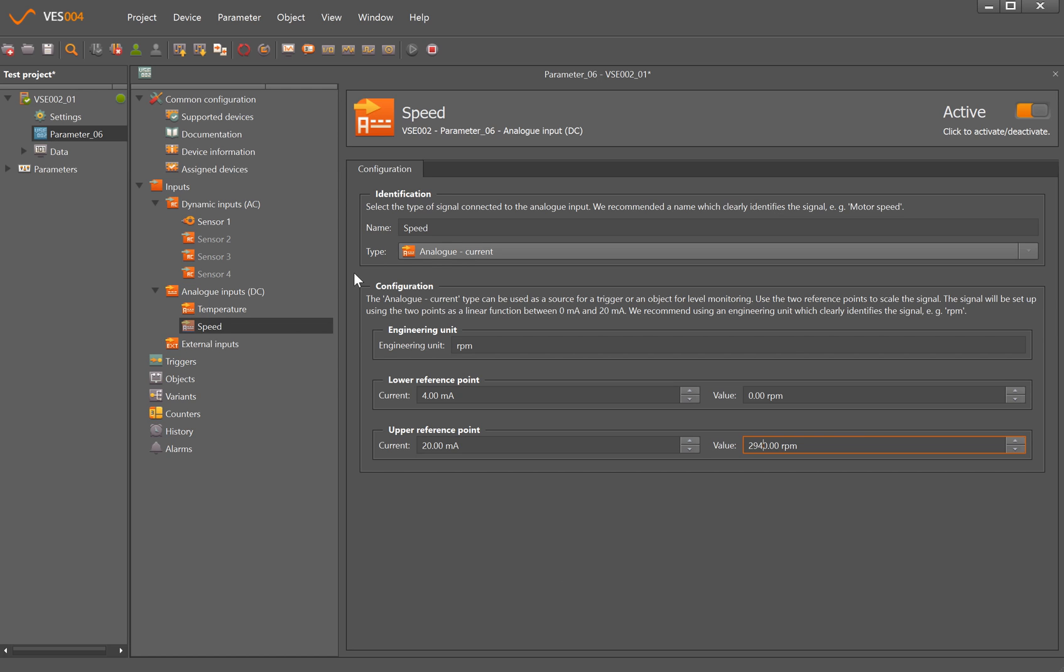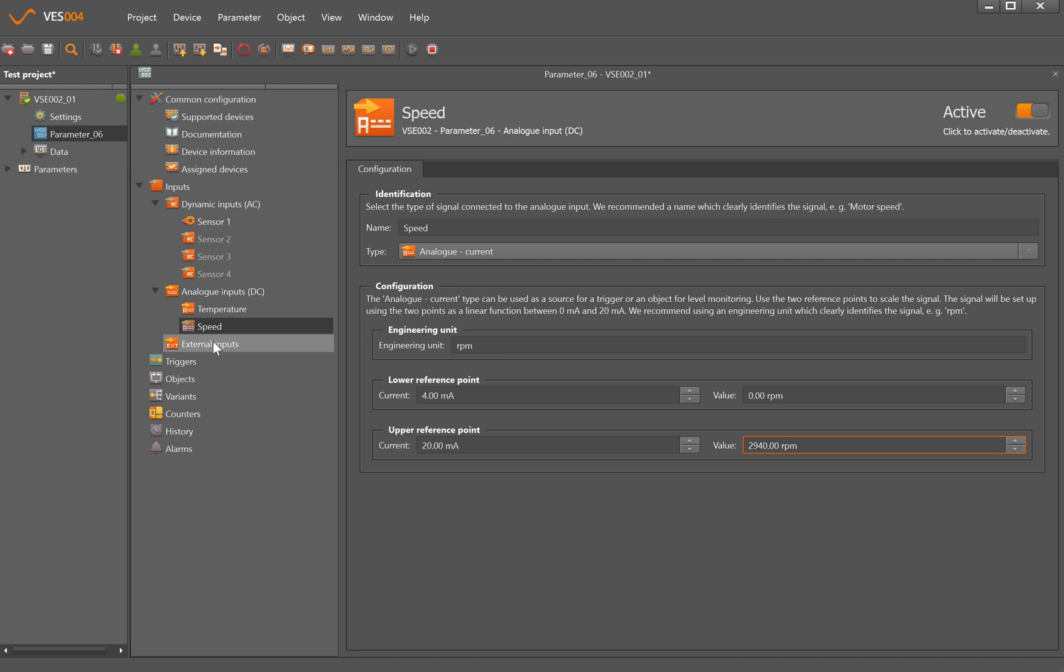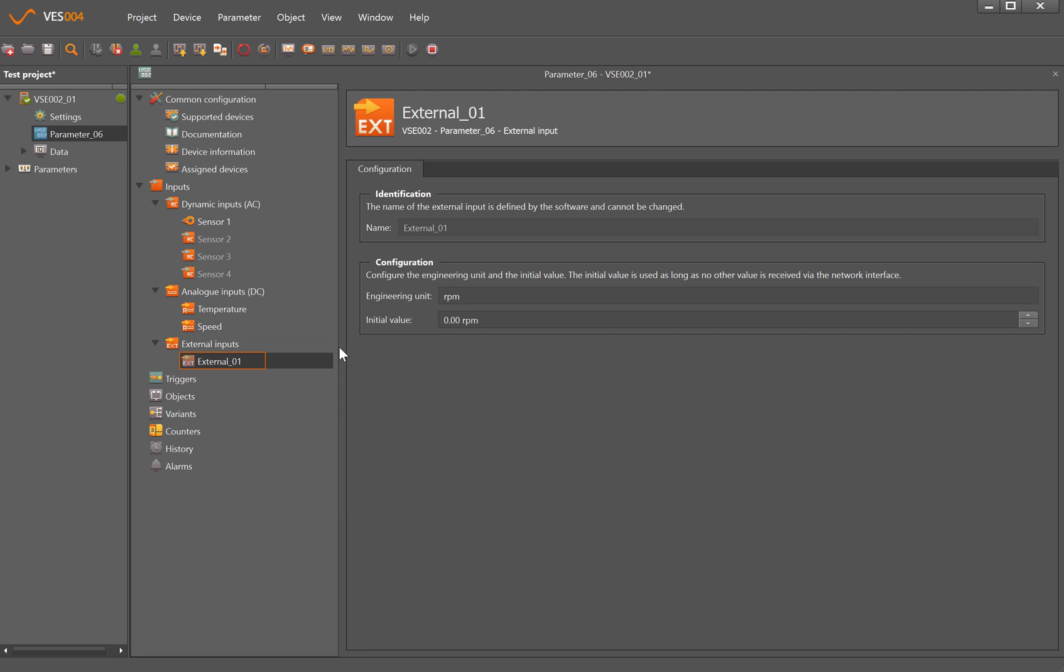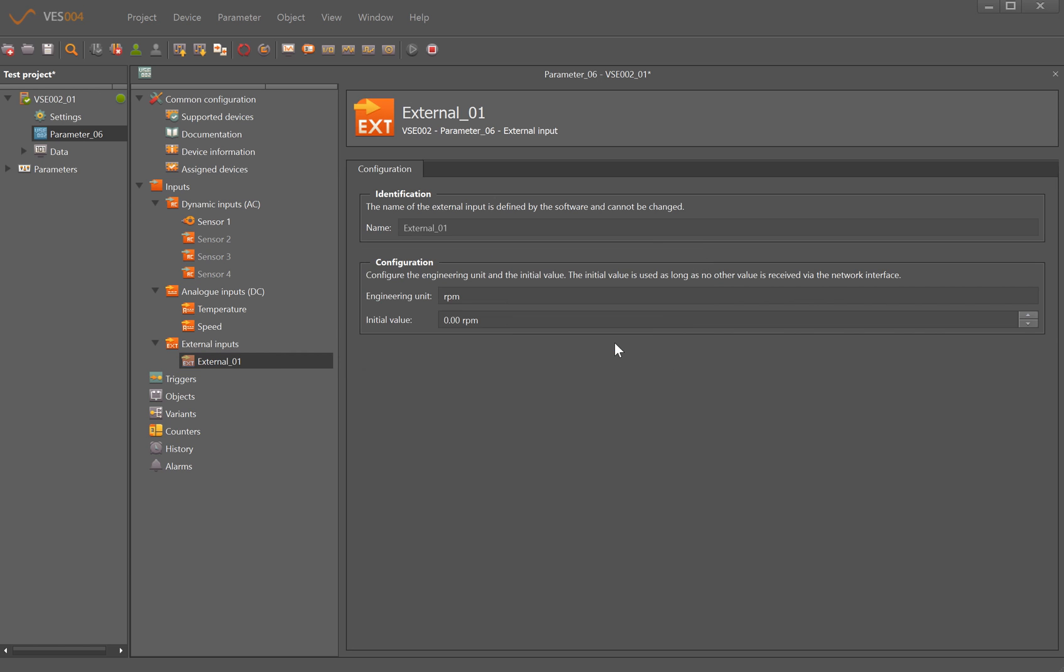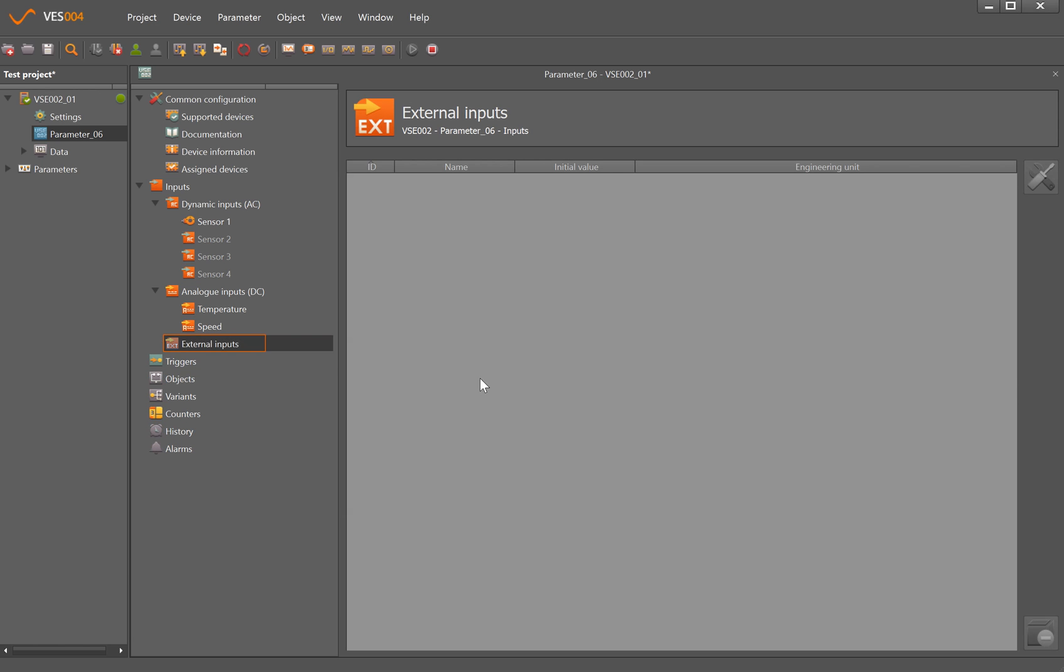So far I've told it that I have one accelerometer input coming on dynamic input sensor 1, a temperature signal coming in and a variable speed signal coming in. External inputs - this would be if we had, say, the system is working over OPC, so we could be sent through from the SCADA system information like speed, but I have that coming in hardwired so I'm going to delete that. If we were working on one of the VSE150 modules, so those are the ones with a field bus interface, you could actually have things like speed information coming over the Profinet or Ethernet IP.